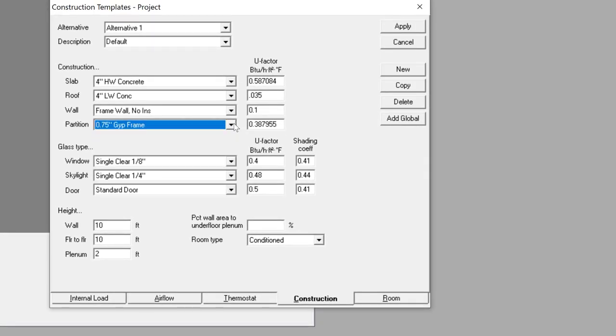For the partition, we'll leave it at the default three-quarter inch gypsum frame. This partition value comes into play if you have an interior space separated by a partition wall where the two zones have a temperature gradient across them. For most load calculations we consider each space to be at the same interior temperature, so there'll be no heat transfer across a partition — but if there was, this partition U-value would be used.